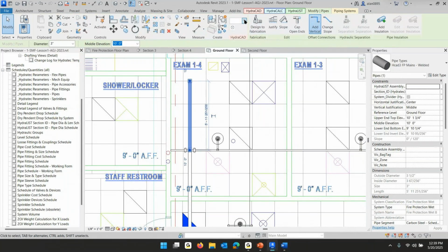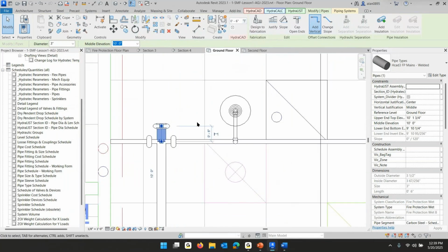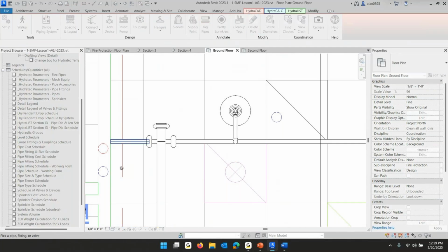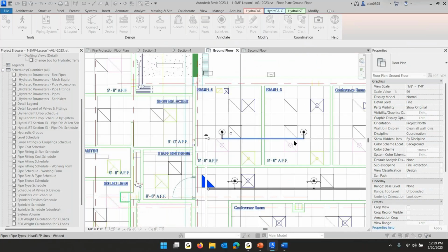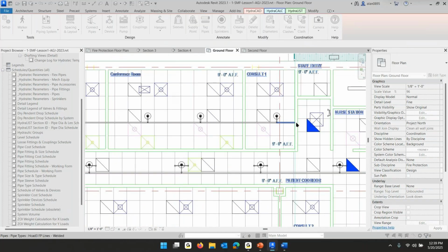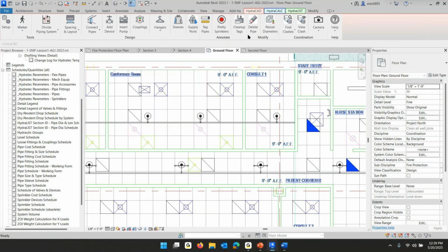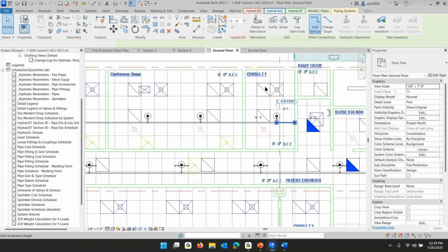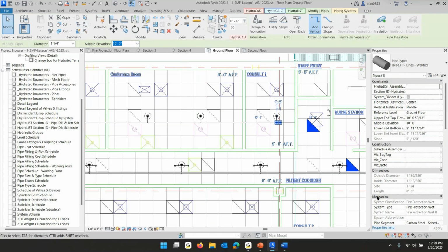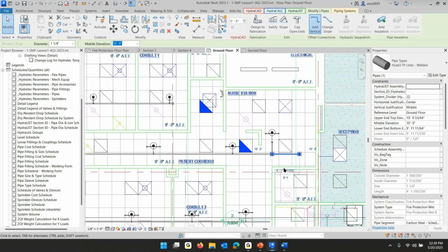I'm clicking on it, and I'm clicking this button to say make it 6 inches and put a cap on it. This one I want to just plain get rid of. So I'm going to click on delete pipe and click on that pipe. It deletes the pipe and fixes the fitting. That's the one I would use on threaded branch lines also, but you see the function there. Then these lines, I want to make 6 inches to a cap. So I'm going to go back to click on that pipe and click on make it 6 inches to a cap.